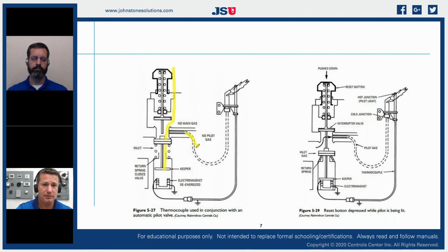It's going to allow gas to pass through our pilot. It's going to warm up our thermocouple. Our thermocouple is going to generate a voltage that is going to energize a winding that is going to hold that plunger open. That's going to allow that valve to operate. As it continues to move, it is now just simply going to pull pressure while the pilot light is operating, and it's going to hold that valve open.